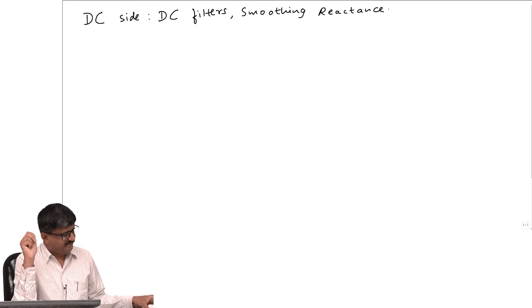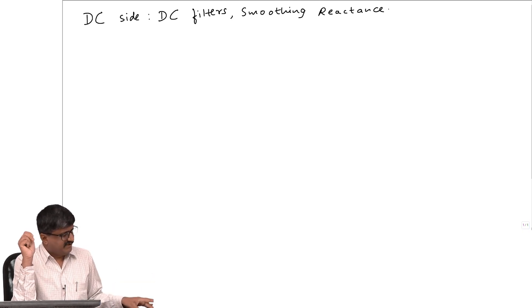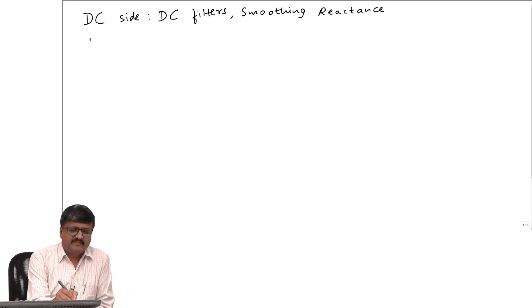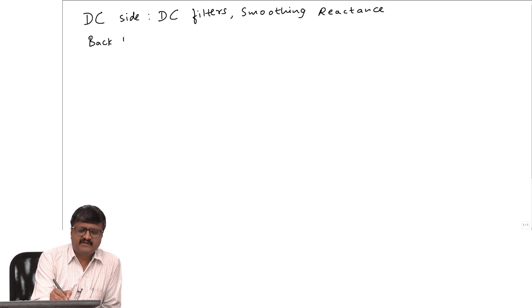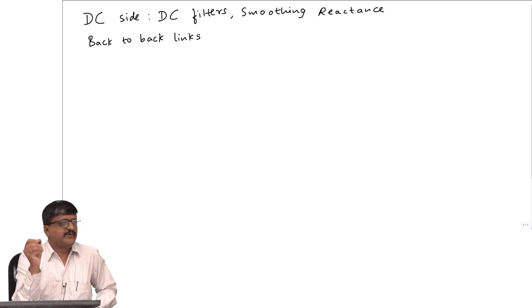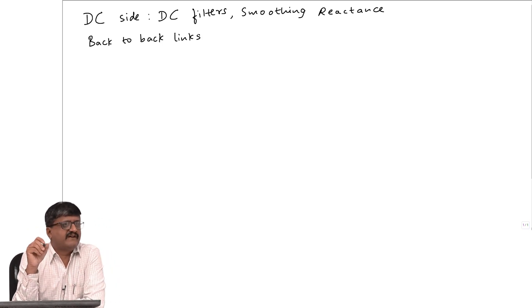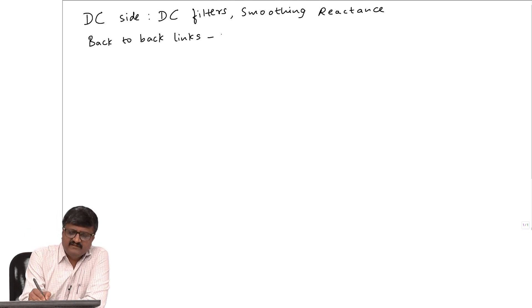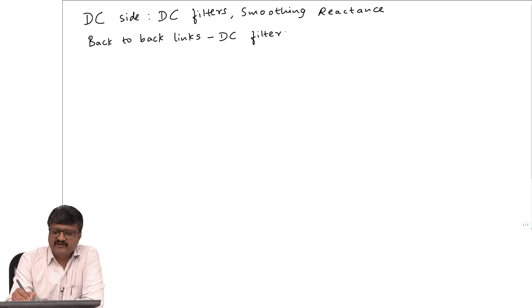I will not get into the details of the smoothing reactor or the other DC filters, but one point to notice: if we have only back-to-back connections — back-to-back links — that means we need to interconnect two systems without having a transmission line. That means the rectifier and the inverter are in the same building. So there is no transmission line; such DC systems are called back-to-back links, and they do not require DC filters.